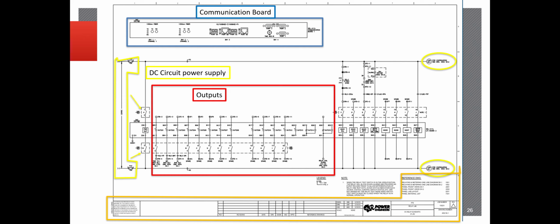On this relay specifically, what's squared off here in red are the relay outputs. These are usually what will send signals to operate the high voltage equipment, such as the breakers, any reclose initiates, as well as the relay failure alarms. The relay failure alarms are usually communication points that go to other relay inputs and will notify them, especially if this relay fails. If it bugs out at all, it will send a signal that the relay failed to another relay, for example, and that will be sent to dispatch to notify them.